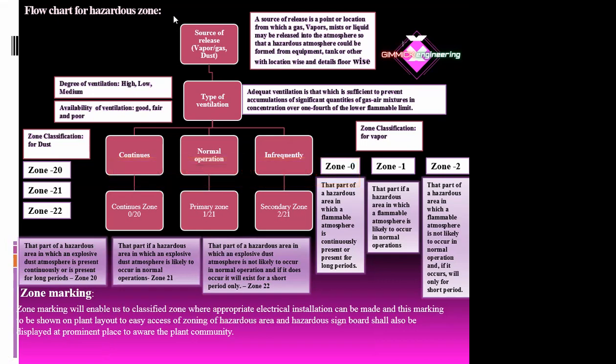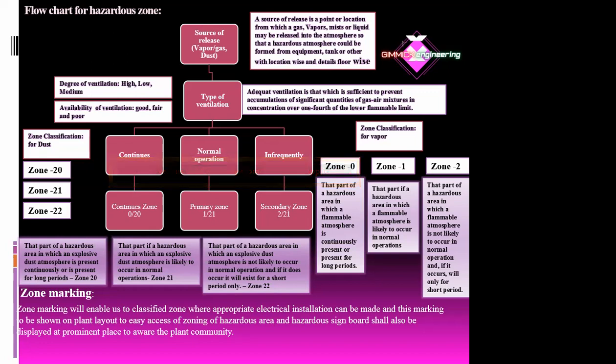Okay. So coming to ventilation, ventilation plays a very important role in mitigating the zoning classification or the zoning area. With a proper ventilation system, we can reduce zone 1 to zone 2 and zone 2 to a safe area. If I brief how ventilation is adequate for reducing the zone area: if 12 air changes or more are maintained, then that area comes under the safe area.